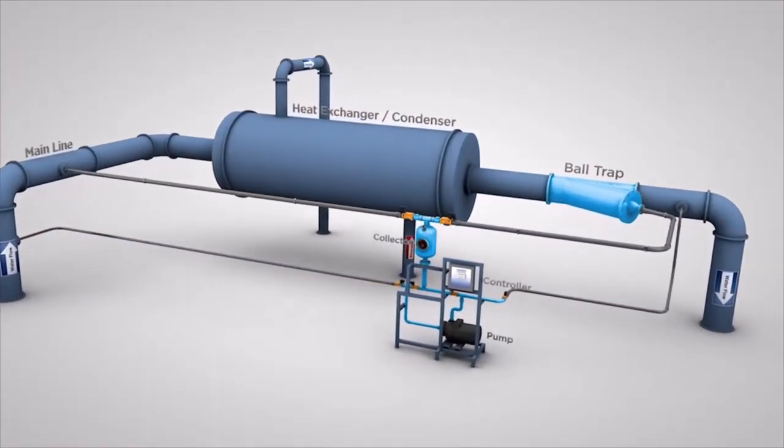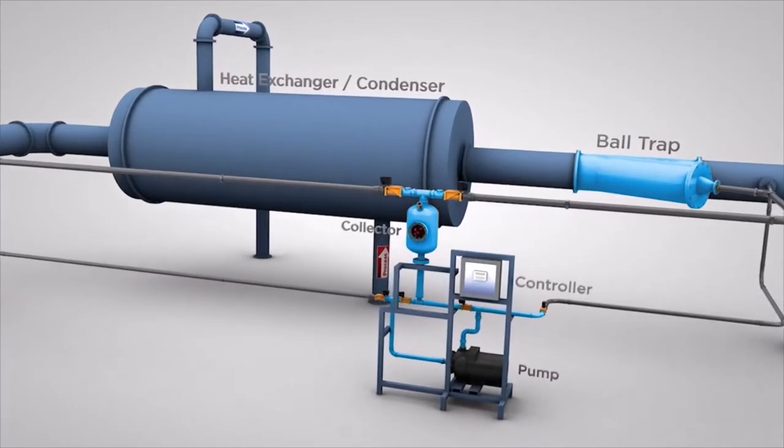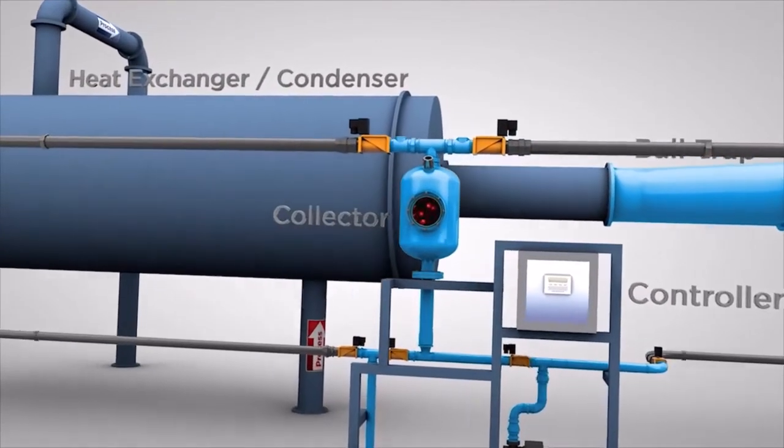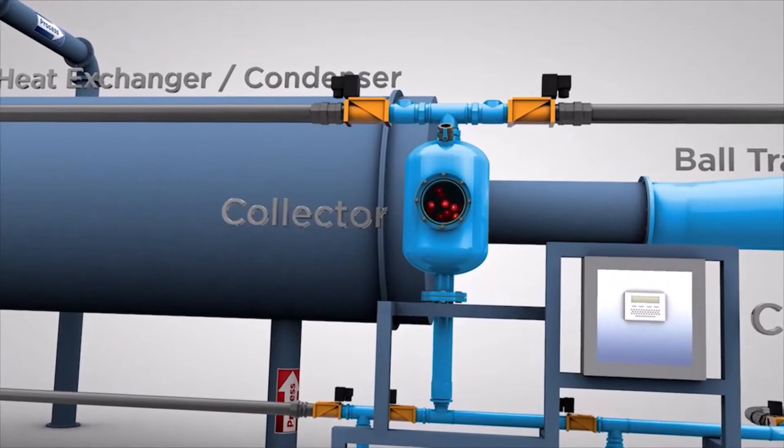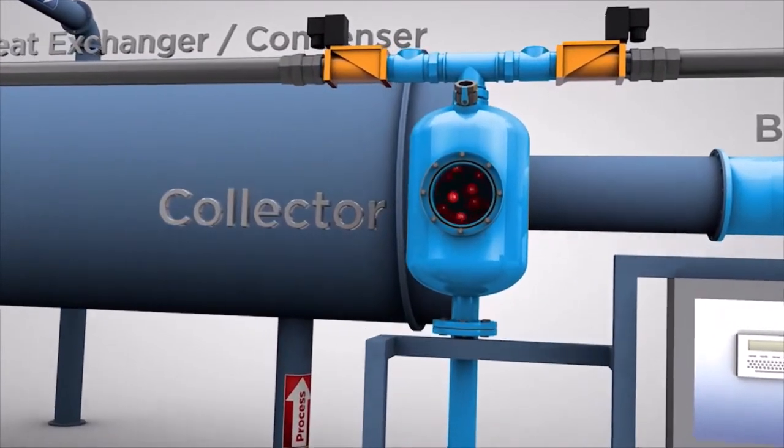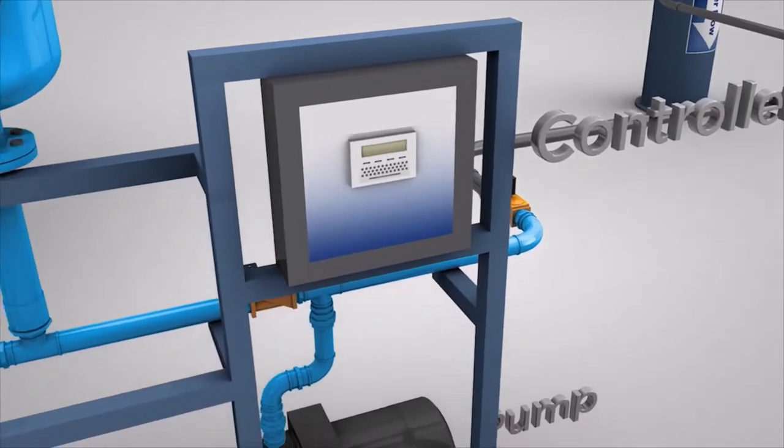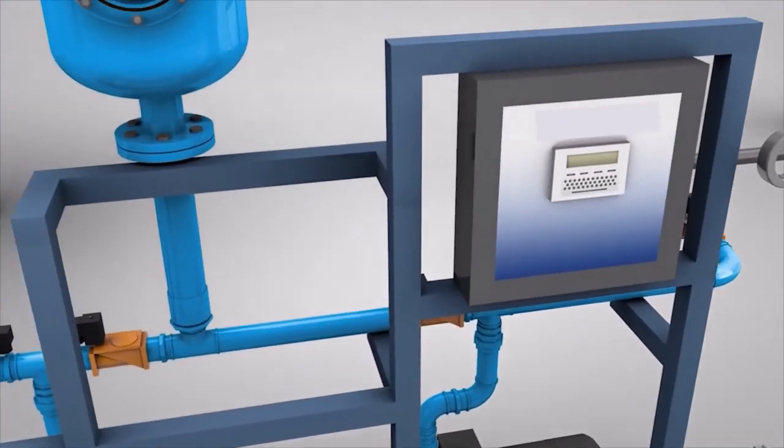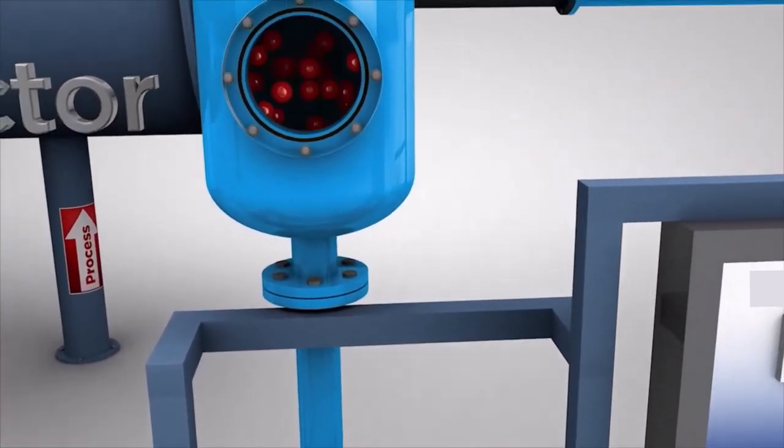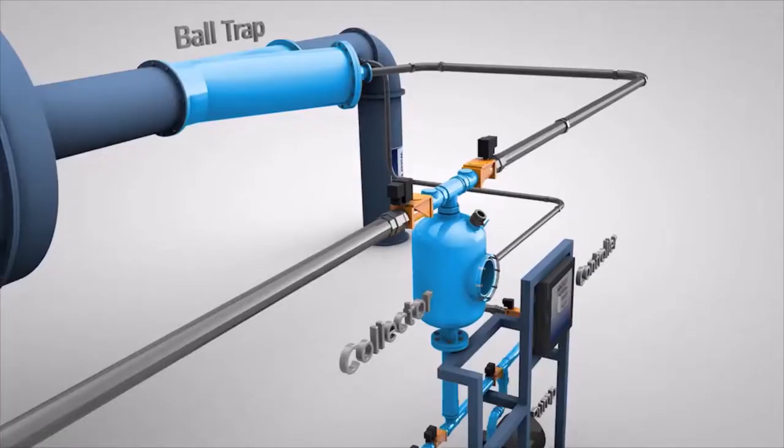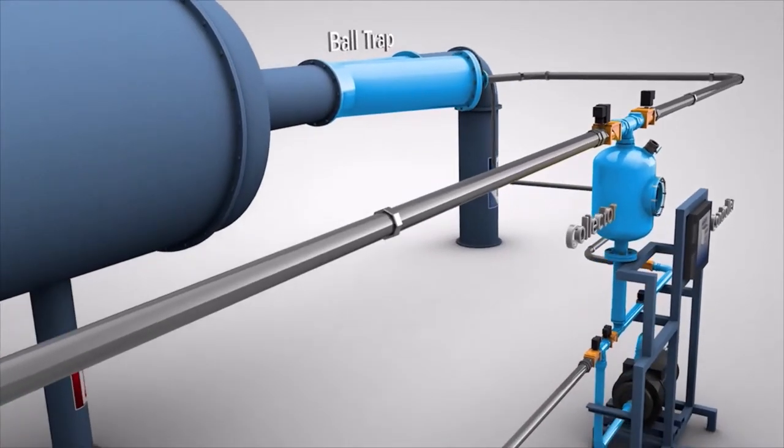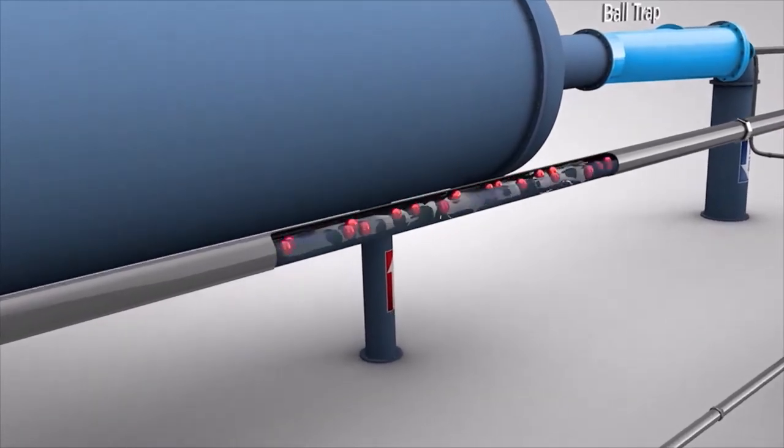The balls start out in a collector that's connected to your heat exchanger or condenser through the system's main line. A window in the collector allows you to easily monitor the condition and amount of balls. Water flows through the pipes and into the collector, where the system periodically injects all of the balls into the inlet pipe at the same time.